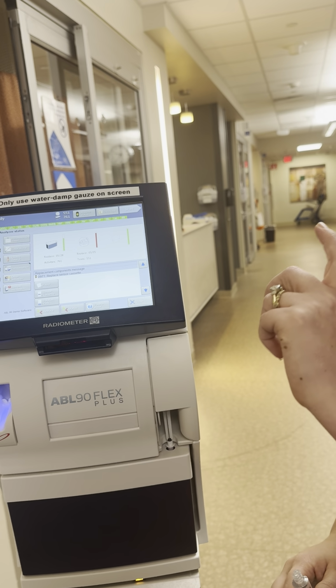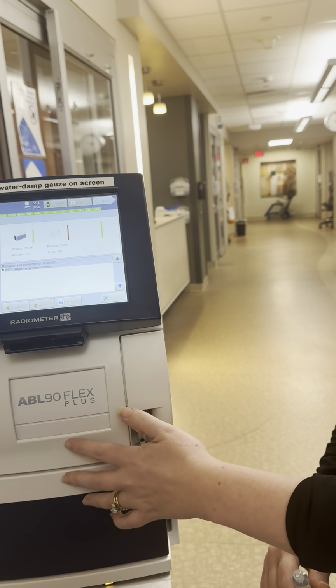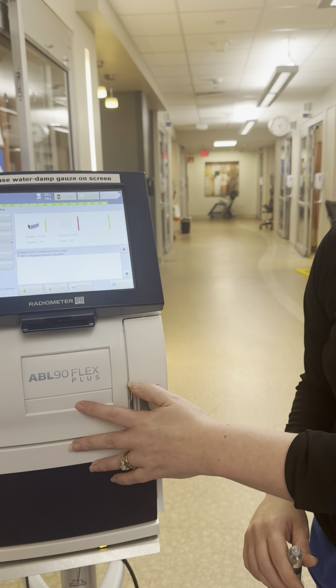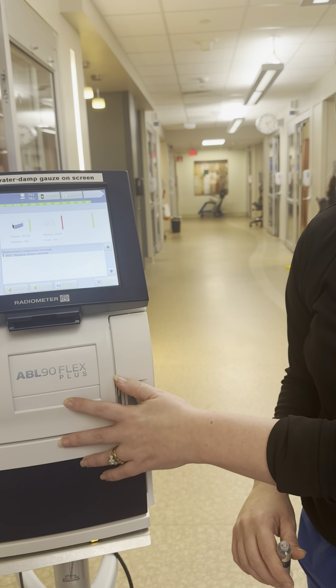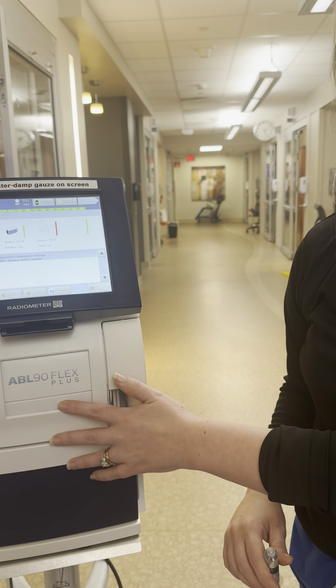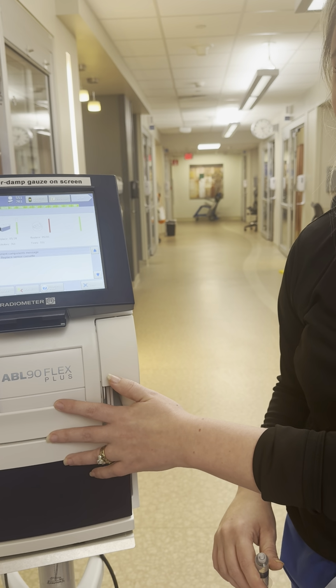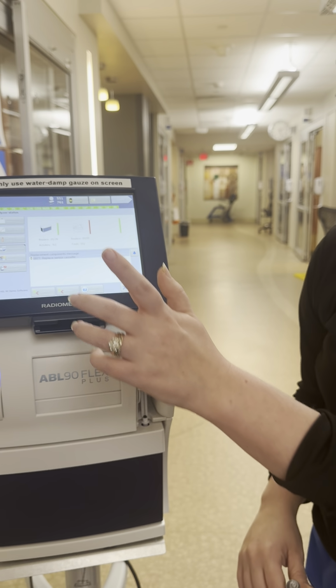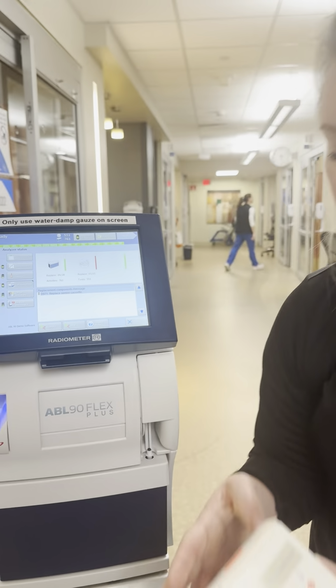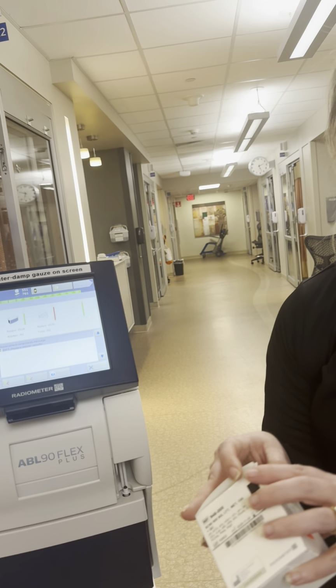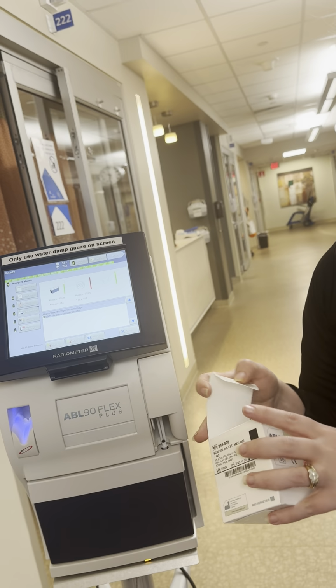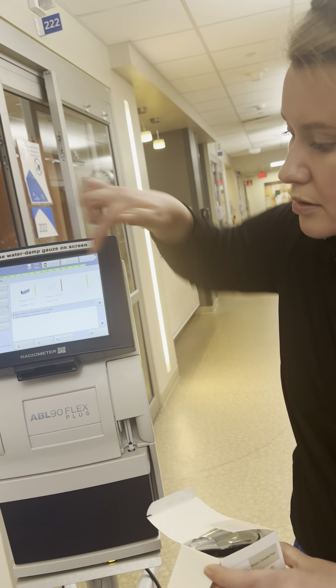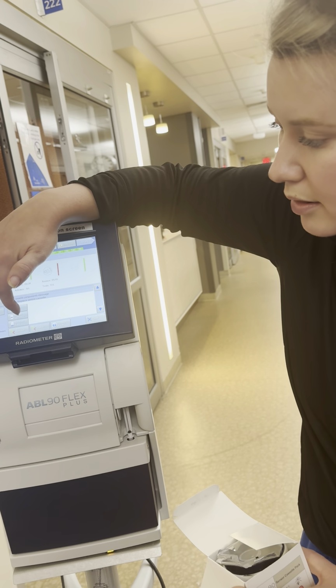There is a little bit of downtime when you are replacing these, so we're going to do a planned downtime. When you are going to replace these, we're going to grab a backup machine and put it on the unit while these are calibrating. They can take a while. Now, it's very easy to do the actual changing process. We're going to walk through the sensor cassette, and then I will show you after this how to do the sample pack. So we're going to hit that we are replacing the sensor cassette.